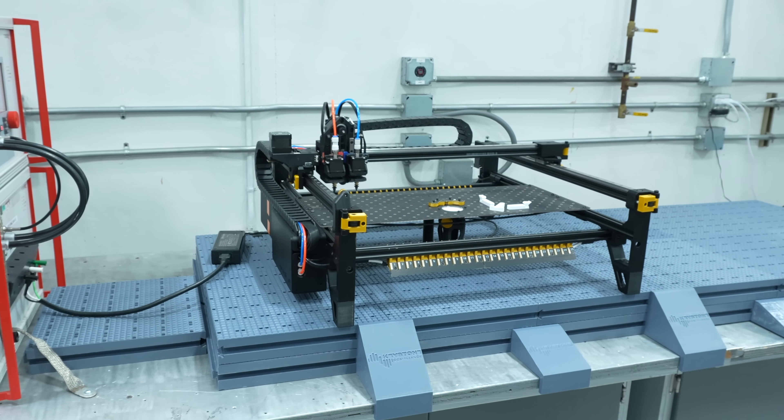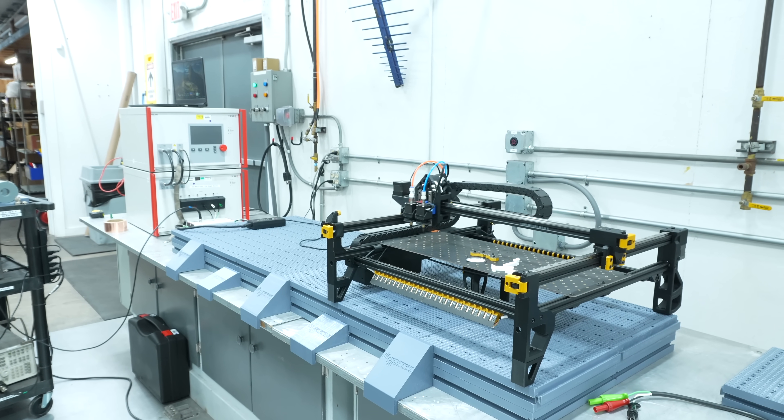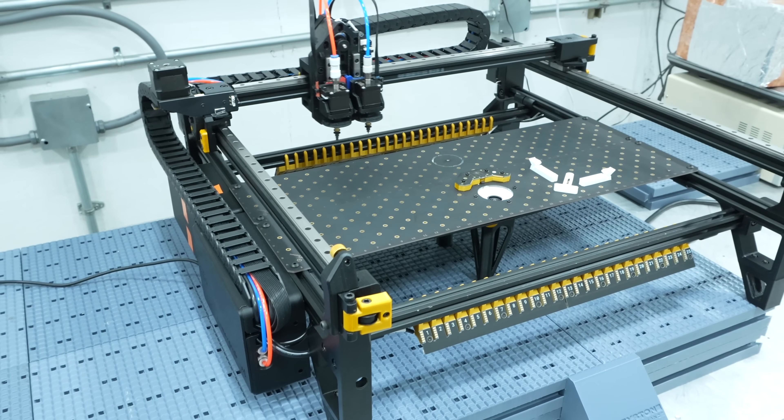In conducted immunity, we effectively blast a ton of high voltage and weird power patterns into the Lumen's power supply and see what happens — do we maintain normal operation? We were three days into our four-day testing program. We were running a test where it would shoot 500 or 1,000 volts into the power supply for 50 microseconds, wait 30 seconds, then do another burst. That pulse was either phase-aligned with mains, 90 degrees off, or 180 degrees off, coupling across all different permutations of line, ground, and neutral. It didn't make it go pop. The Lumen took 2,000 volts through mains — no problem, kept on working.